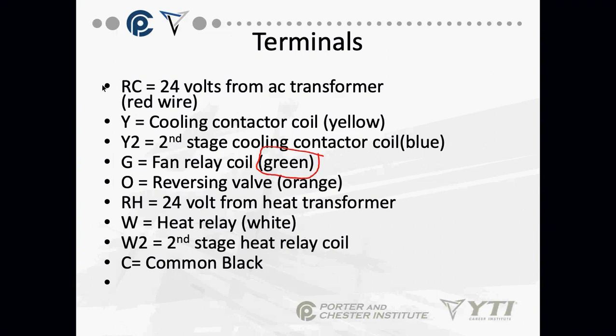There's three terminals you never want to have connected together. You don't want them touching. You don't want the wires close to it. Very important: RC, RH, and C. These terminals can never be wired together. If you wire any of the R's together and have it touching the C, okay, either one of these R's touching the C, you're going to short out your transformer.